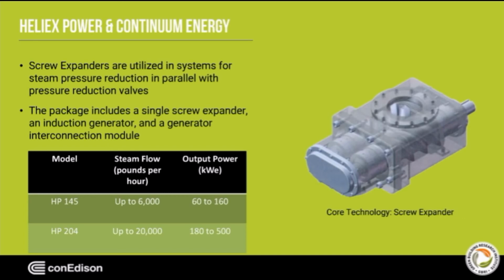The screw expander set is made up of a single screw expander, an induction generator, and a generator interconnection module. There are two models available, as you can see here, the HP145 and the HP204. The HP145 is a better fit for customers that have smaller steam loads, especially during the summer, while the HP204 will be a better fit for our larger customers. Each model is available to generate a range of electric output dependent on the steam input.